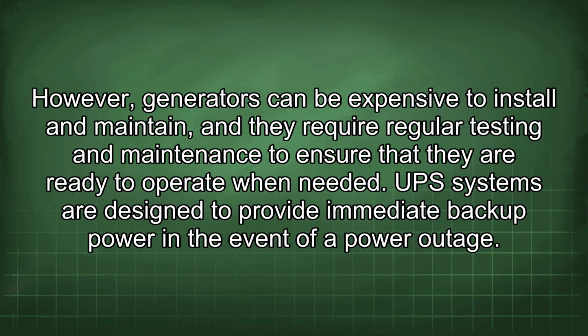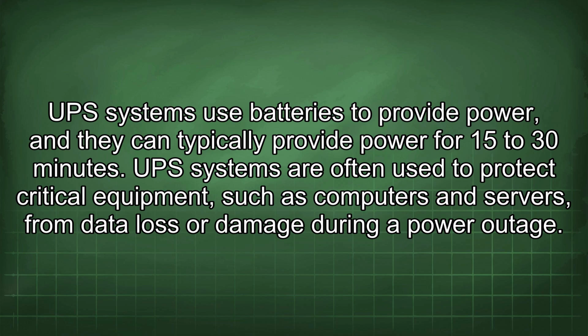UPS systems are designed to provide immediate backup power in the event of a power outage. UPS systems use batteries to provide power, and they can typically provide power for 15 to 30 minutes. UPS systems are often used to protect critical equipment, such as computers and servers, from data loss or damage during a power outage.